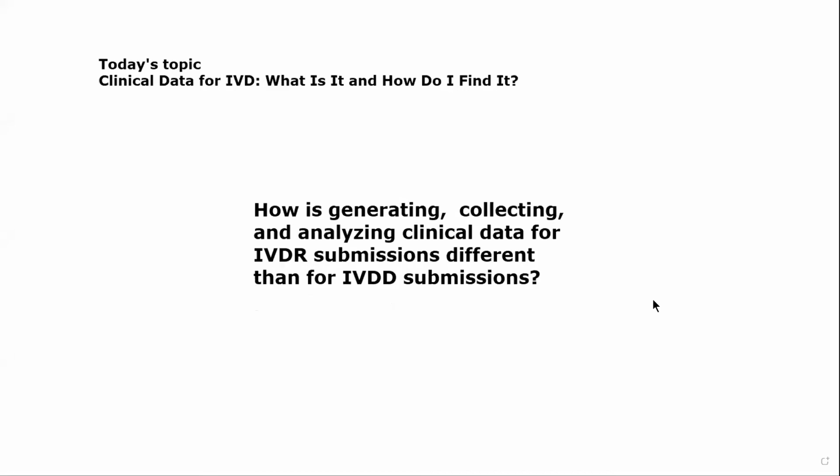How is generating, collecting, and analyzing clinical data for IVDR submissions different than for IVDD submissions? In this case, IVDR is going to have much more of a reliance on clinical data. Up until now, you've really been focused on collecting the performance data in terms of the analytical performance. So the main difference, in terms of what we're all familiar with in IVDD, is that the analytical performance is kind of where we've stopped.